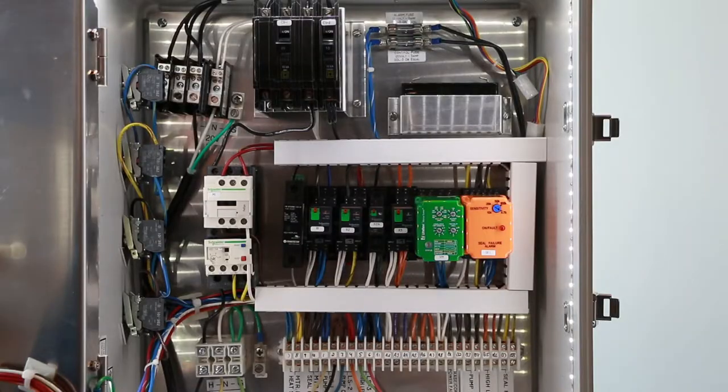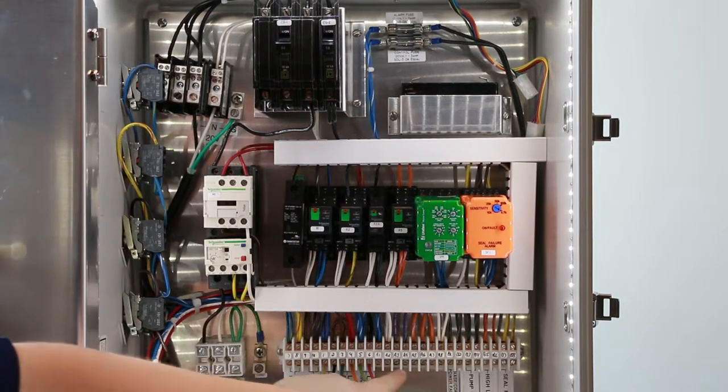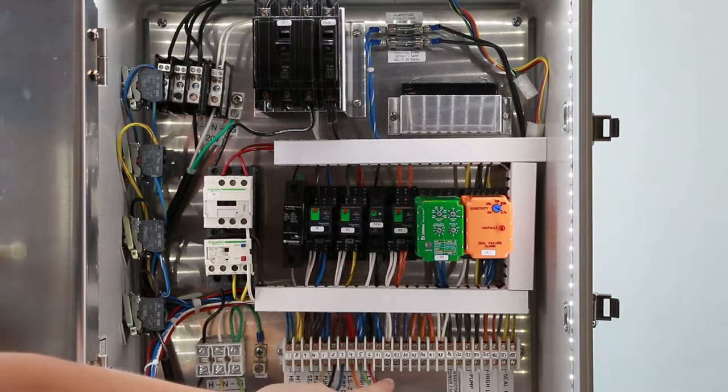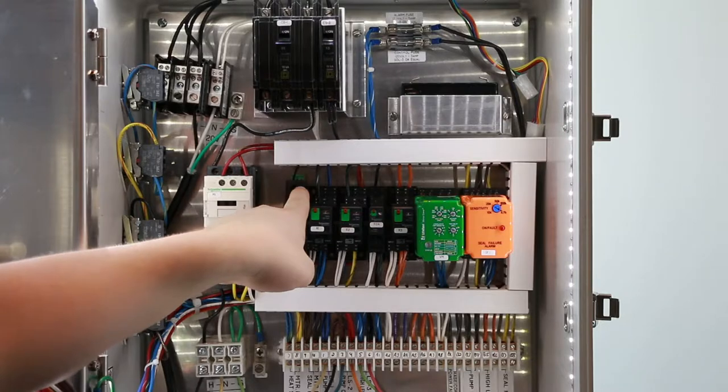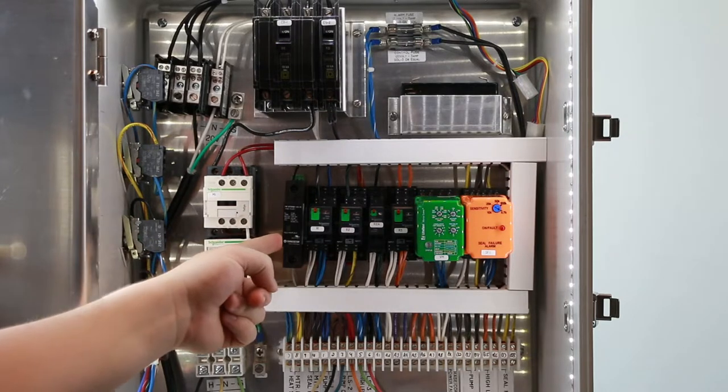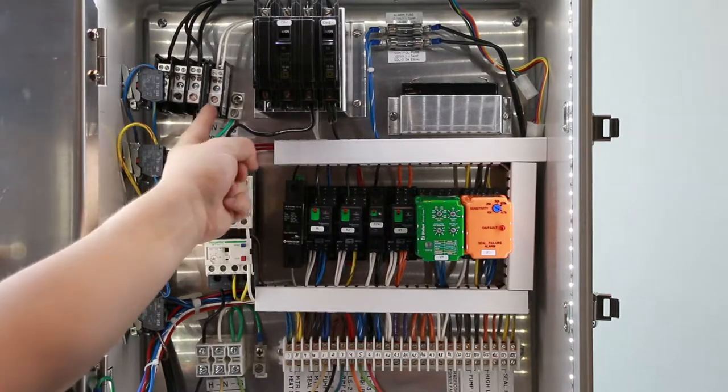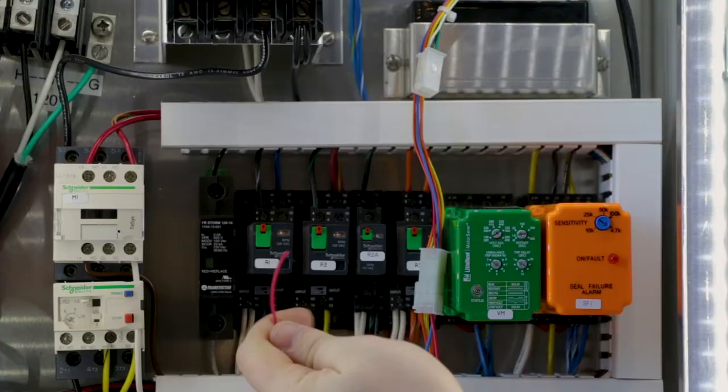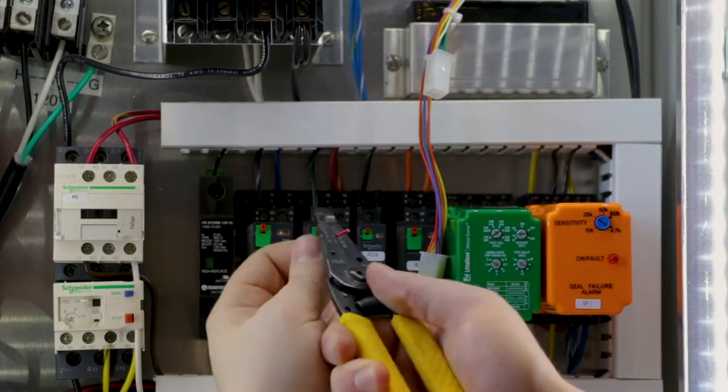You will now want to identify where each of the wires from your wiring harness will land inside your panel. The red and blue leads will go to the two terminals on the battery. The orange and yellow wires will go to alarm contacts within your panel. The black lead will land on a 120-volt source. In this panel, we are using the lightning arrestor. The green lead will land on the panel ground, and the white lead will land on the panel neutral. Cut the leads to length to reach the appropriate places in the panel, then strip the ends.